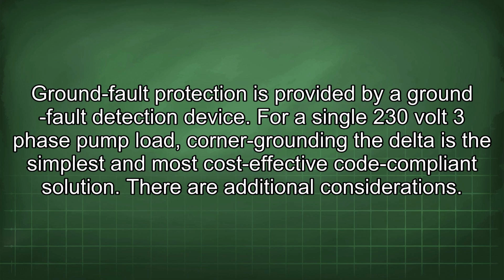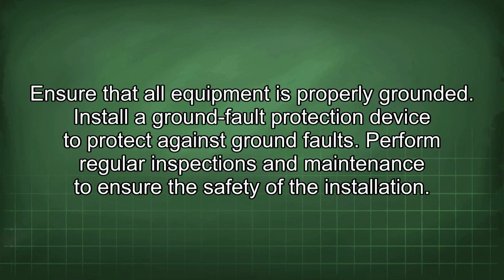For a single 230-volt three-phase pump load, corner grounding the delta is the simplest and most cost-effective code-compliant solution. There are additional considerations. Ensure that all equipment is properly grounded. Install a ground fault protection device to protect against ground faults. Perform regular inspections and maintenance to ensure the safety of the installation.